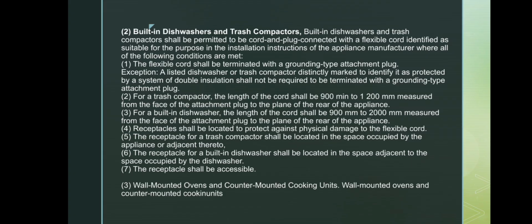Second, for trash compactors, the cord length must be between 900 millimeter and 1200 millimeter, measured from the plug to the back of the appliance. For built-in dishwashers, the cord length must be between 900 millimeter and 2000 millimeter, measured the same way. Fourth, the receptacle must be placed where the cord is protected from physical damage.